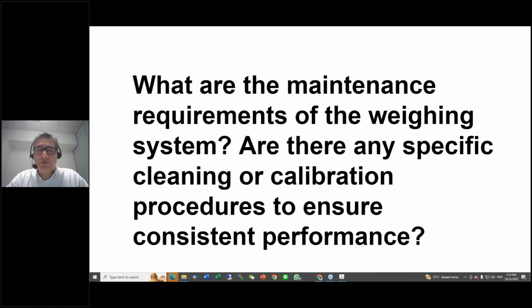But checking the scale is something that can be done free of charge without losing any production time, every day. So that could be a starting point. Then making a calibration maybe every month or every 6 months could make sense to give more consistency in the production check. But at the end of the day, it's just to be sure, because the load cell keeps its calibration for a long time. Maintenance activities, as I mentioned before, are limited.